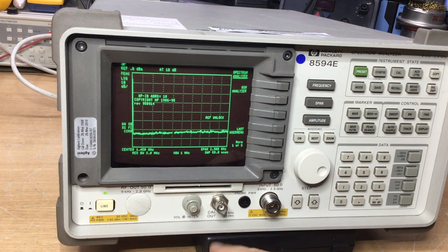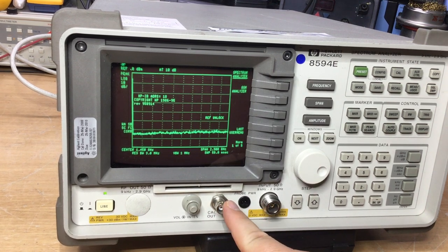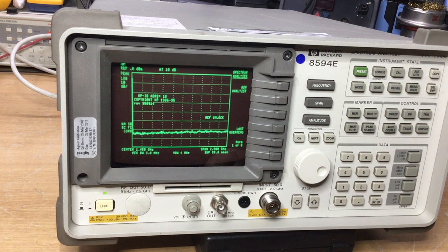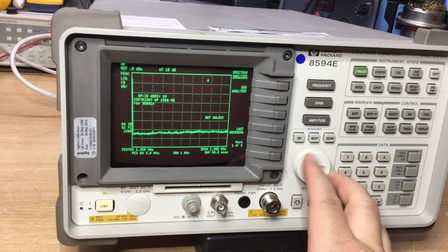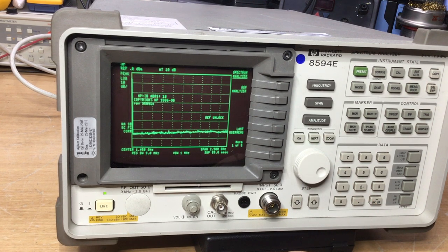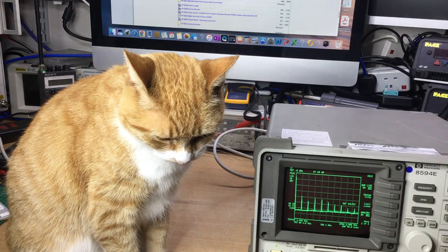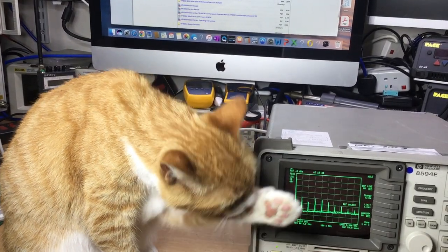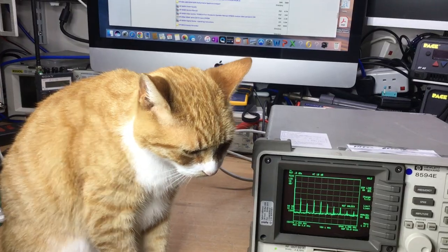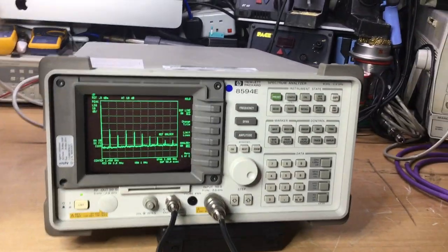What we can do is try a calibrate by linking these two ports together. We'll see what happens there and what faults there are. I think there's a fault log in it as well, which I'll need to find. Then we can look further to see if there are any fault codes stored and what they might be, which might give us a better indication of what's going on. We'll link these ports together and run a calibrate routine to see whether that shows any errors too. So bear with me. Okay, we're joined by the technical manager, who's no doubt going to advise us at some stage what the fault may be with this Spectrum Analyzer.